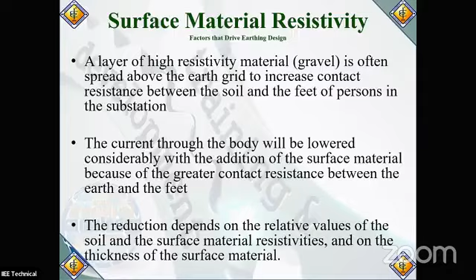Okay. Design drivers. Ang pinakamalaking driver dyan is symmetrical fault current. So that's why mas gusto kong sabihin, when you do IEEE 80, dapat marunong ka rin mag-short circuit. Baka mamaya hindi mo masolve to pag hindi ka marunong mag-short circuit. Because what is crucial here is what is the zero sequence current that is passing to the ground. Yun lang naman ang pinag-uusapan dyan. Paano ma-determine yan? Well, of course, it can be done through the symmetrical method, or there are a few things that can shorten this calculation. But the most important driver of the design is to understand what is the symmetrical earth fault current that is present or might be present within the system.